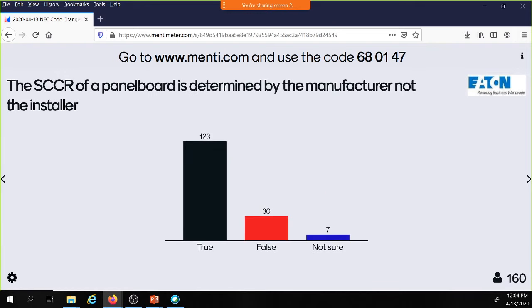Here we go. The short circuit current rating of a panel board is determined by the manufacturer and not the installer. 124 say true, 30 say false, and 7 are not sure. Well, I'm going to give you my perspective on this one. When it comes to a panel board, yes, the manufacturer will put some information on the inside of the door, and we test, and we know what the short circuit current rating capabilities are of that panel board. But the short circuit current rating of the assembled unit when it's installed is determined by the installer and not the manufacturer. We're going to talk about that in detail.